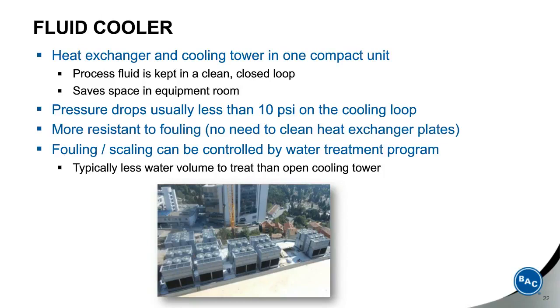There's no need to clean heat exchanger plates, as the fouling and any scaling can be controlled through the water treatment program. The external surface of the coil is very open, and the water can get in there, and the water treatment chemicals can get in there and take care of any fouling or scaling on the surface and keep them performing at peak efficiency.